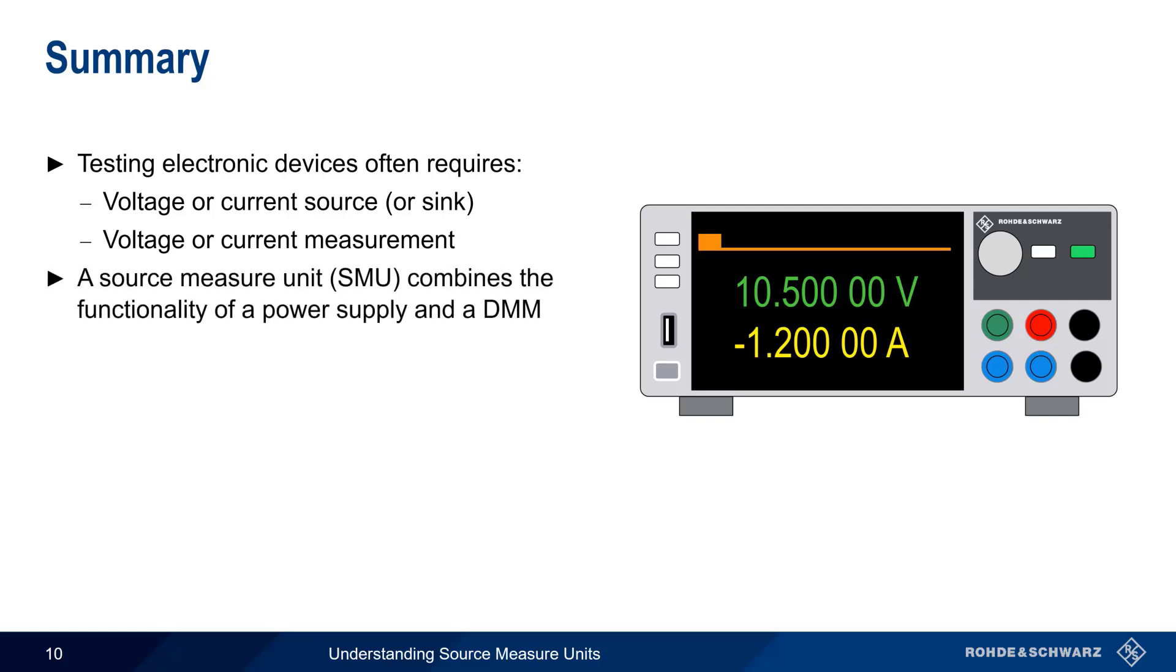Let's summarize what we've covered in this presentation. Testing electronic devices often requires two things, a source or sink of voltage or current, and a means of measuring voltage or current. Traditionally, these two requirements were met using separate instruments, but more recently, these functionalities are being combined into so-called source measure units or SMUs. Furthermore, the design of most SMUs allows them to be operated in all four quadrants, meaning they can behave either as a power source or as an electronic load.